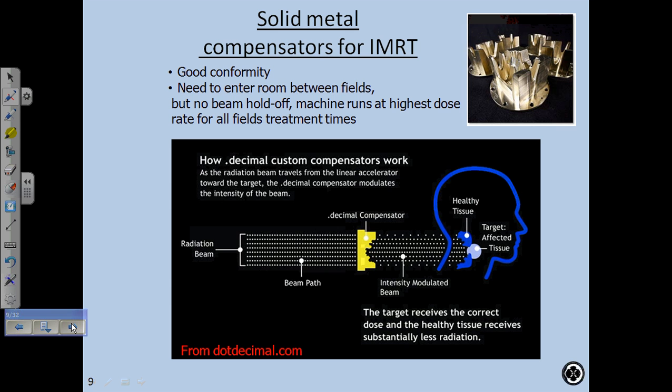for IMRT. This is something else. This is not that common, but it's used for facilities that want to do IMRT on a machine but don't have the financial ability to upgrade the machine to an MLC-based machine. So this machine just has jaws, maybe asymmetric jaws, and what they can do is all their inverse planning, and then instead of saying create the MLC shapes, they're going to order a compensator.